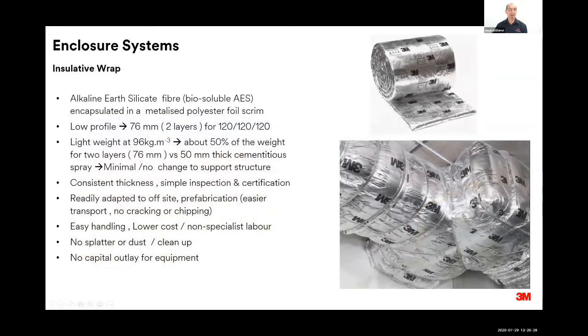And finally, flexible insulated wraps. Our product, the 3M 615 Plus, is an alkaline earth silicate fibre that's encapsulated in a metallised foil scrim. It has a low profile, with 2 layers for 2 hours. Lightweight at 96 kilograms per cubic metre, about 50% of the weight of sprays, for example. So there's minimal to no change to the support structure, and a consistent thickness for easy inspection and certification.